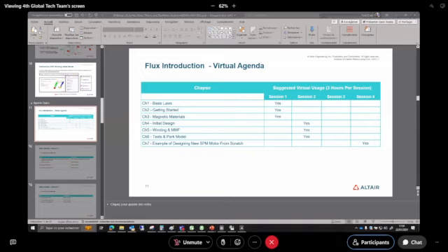In Flux Motor there is no mechanical stress, and this is why I didn't include it here. But you are right: when you optimize a motor, mechanical stress is really important, because from a magnetic point of view you can have a good motor, but from a mechanical point of view it may not respect the stress limits on the bridges of the rotor, for instance.